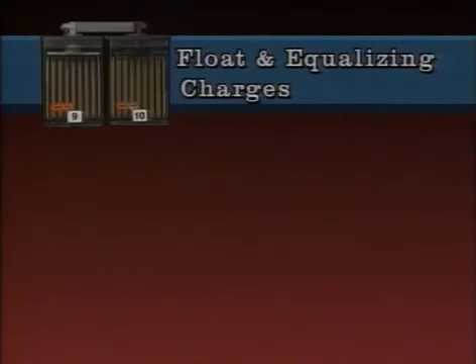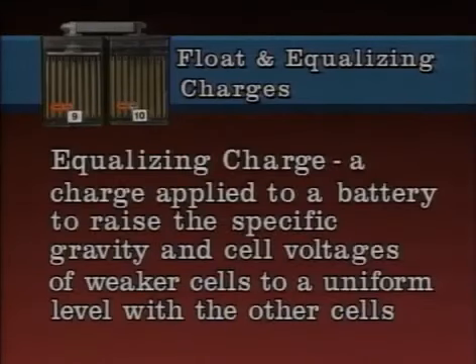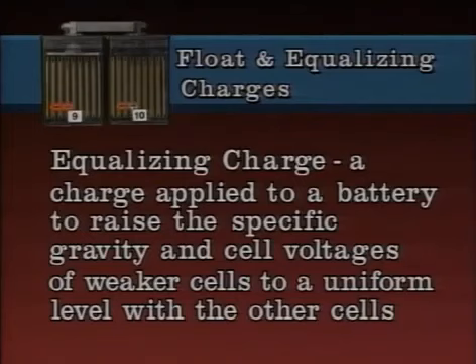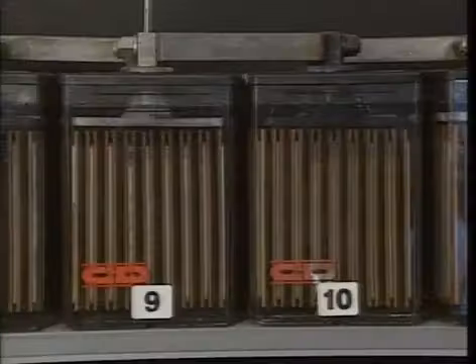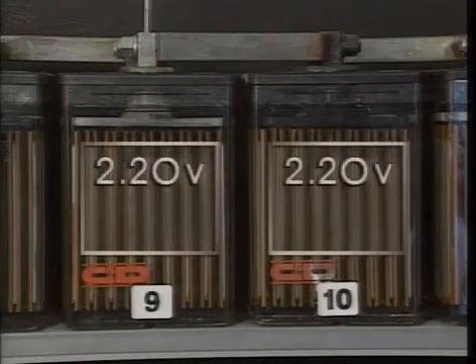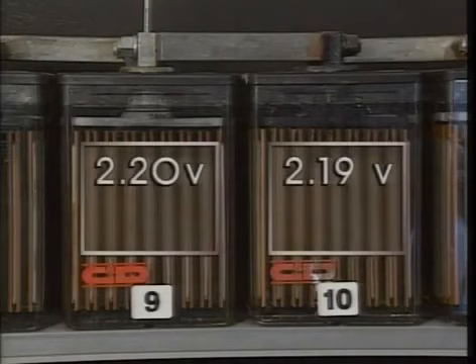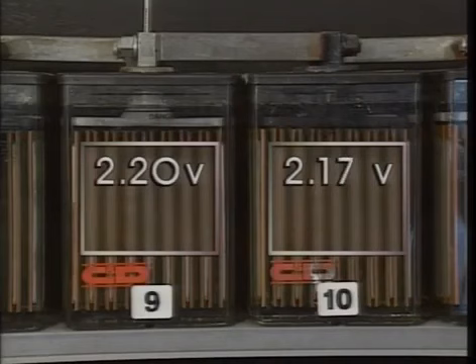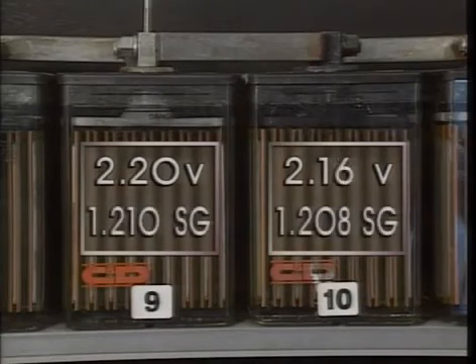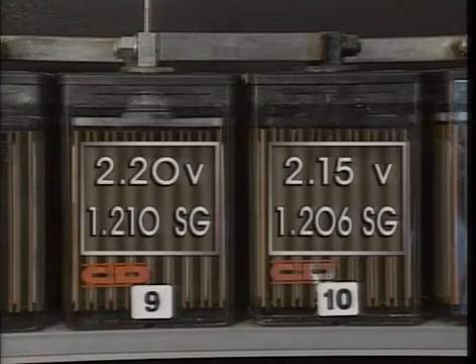Another type of charge that may be applied to a battery is an equalizing charge. An equalizing charge is applied to a battery to raise the specific gravity and cell voltages of weaker cells to a uniform level with the other cells. When battery cells are in service, the cell voltages tend to become unbalanced — the voltages of some cells fall below the level of the others, and specific gravity will begin to fall along with the voltages.